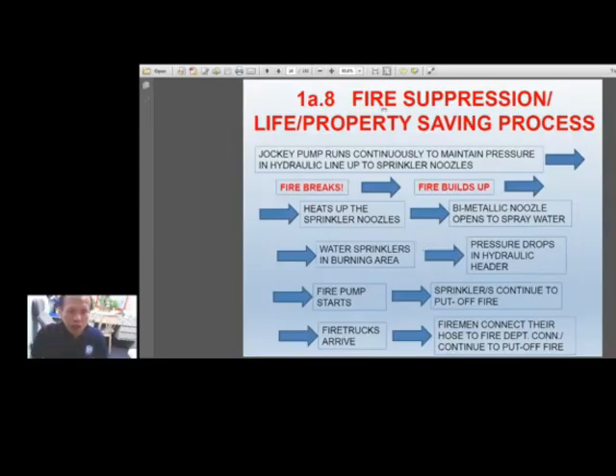The next slide is fire suppression. After the life-saving process, we have this fire suppression and life and property saving process. So as usual, in a building that has an automatic fire sprinkler system, your jockey pump is always running every now and then in order to pressurize the hydraulic system, meaning the sprinkler system of the building. So the jockey pump runs, and then when suddenly there is a fire, the fire builds up and heats a sprinkler that is just above the fire. The sprinkler will then operate because it works like a bimetallic spray nozzle.